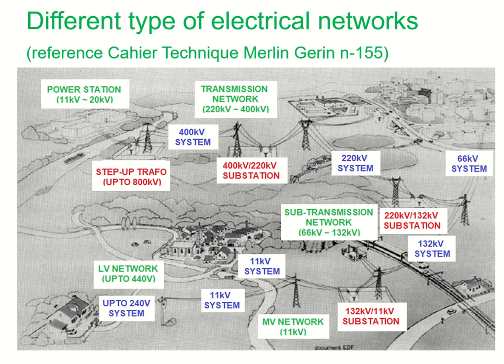Different countries use different standards. Mostly power is transmitted at a level of 220 kV to 400 kV, and this kind of network is called the transmission network. When the power reaches a point near to the consumer side, we can reduce it from 400 kV to 220 kV again using transformers at substations. Then it is transmitted to the sub-transmission network, nearer to consumers like industrial consumers, where the power is reduced to a level of either 132 kV or 66 kV.